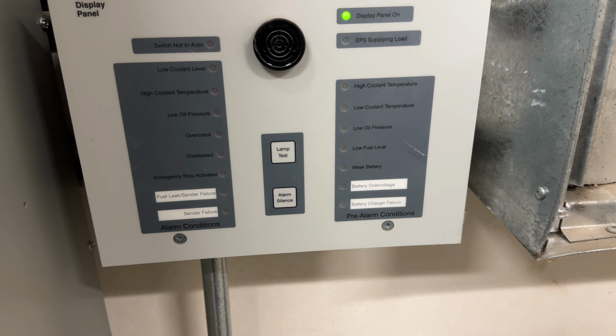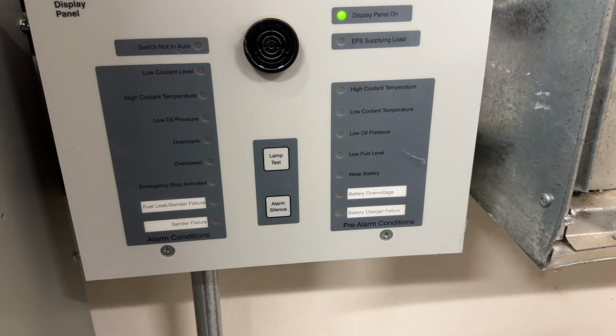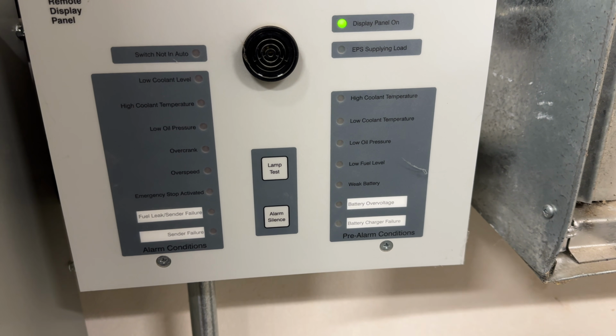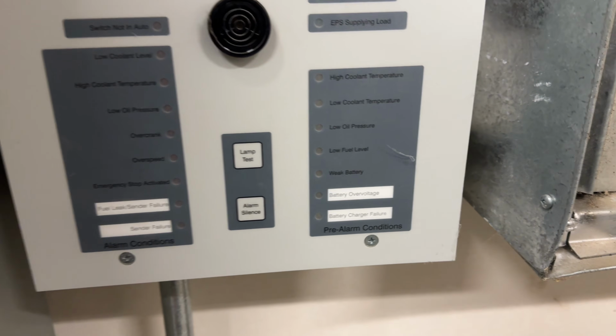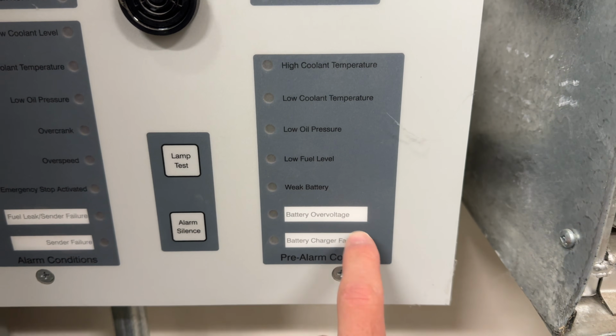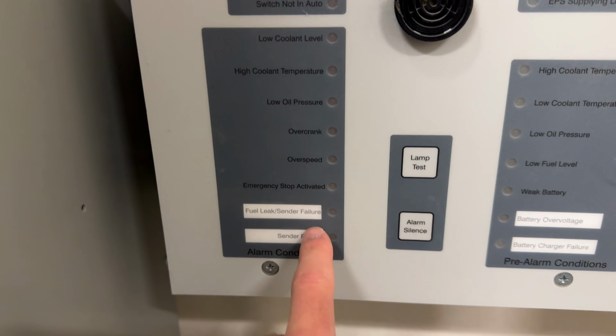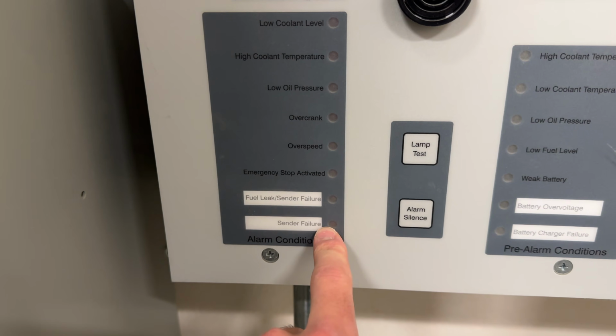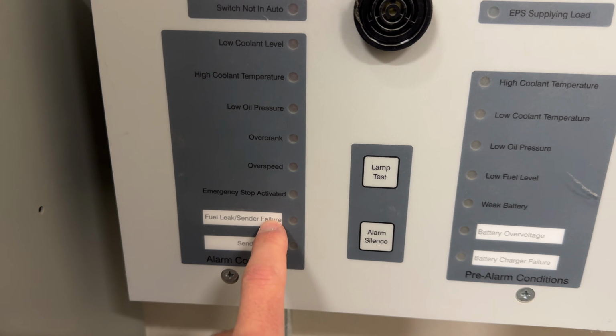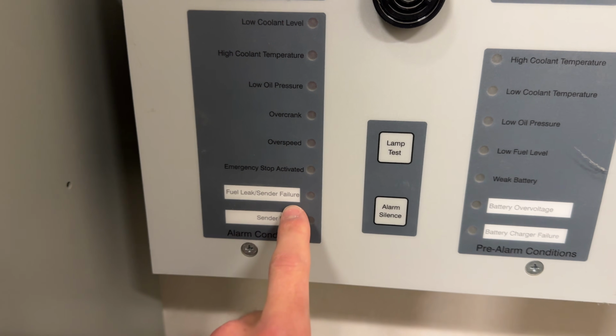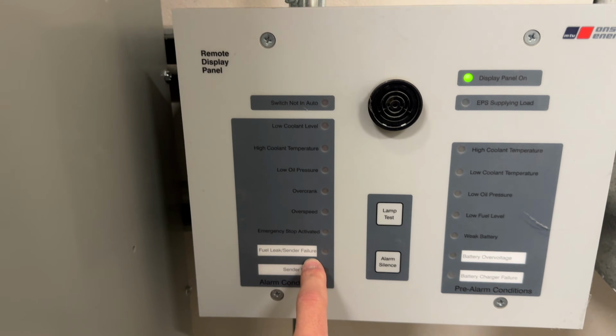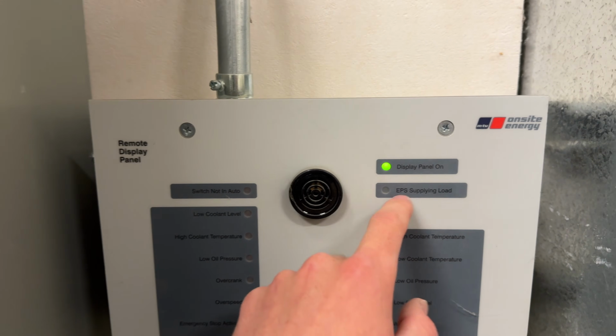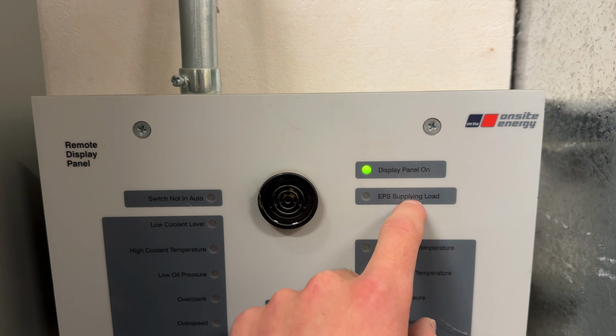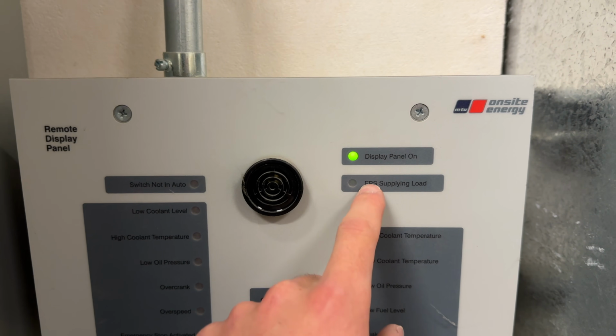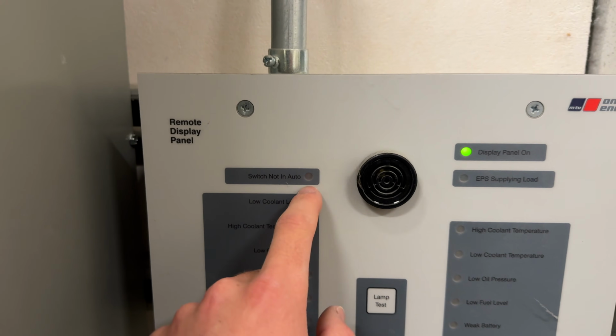And we have high coolant temperature, low coolant temperature, low oil pressure, low fuel level, a weak battery, battery over voltage, battery charger failure, and then sender failure. Honestly, don't know what that is. Fuel leak sender failure. Yeah, not exactly sure what this is. I'm guessing this would have been up if this would have been lit up earlier when we were running, but I didn't see. Switch not in auto.